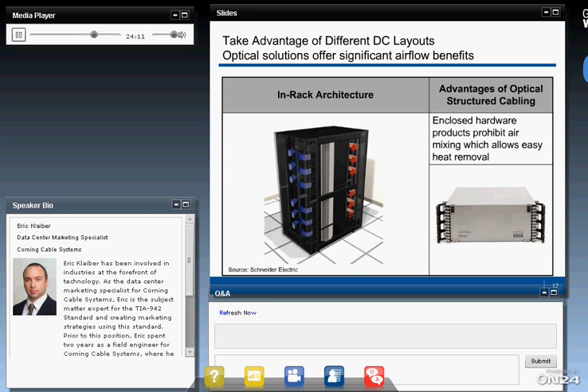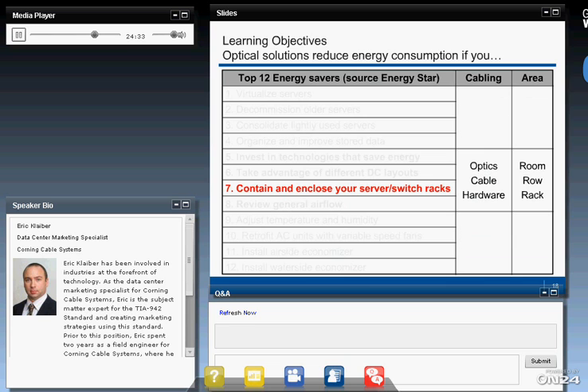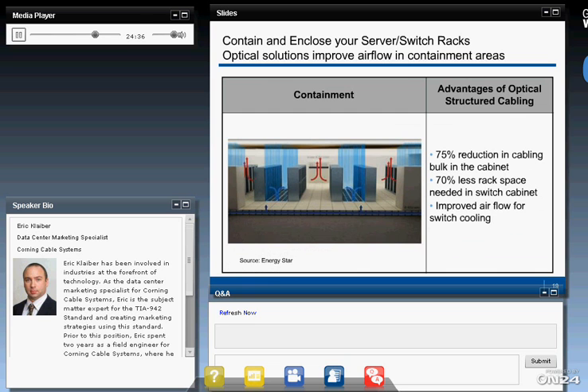So you have to have the ability to block the airflow in all other spots other than where you want the air to pass through. And so you need a set of hardware that allows you to block it. So you have to have an enclosed set of hardware. So now we want to contain your actual hot aisle and cold aisle. There are different ways to do that. You can do chimneys. You can do regular hot aisle containment, cold aisle containment. It doesn't really matter as long as you're doing containment.